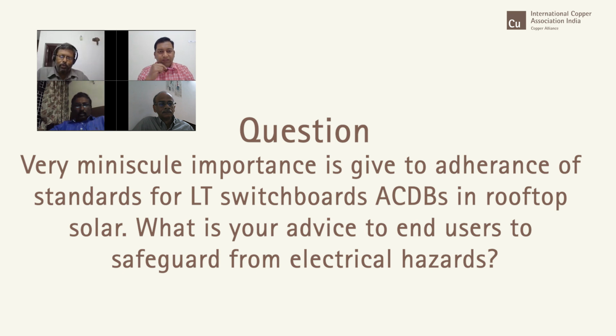The AC distribution board in a solar environment is peculiar in one way, that it is a bidirectional device. The power flows in either direction. So to that extent, the components and devices used in that particular switchboard shall also have those features. For example, if you are using a current sensing device, a residual device, then the directional flow of the current matters. So such aspects need to be taken care of in the panel manufacturing, because it has to be a bidirectional device.